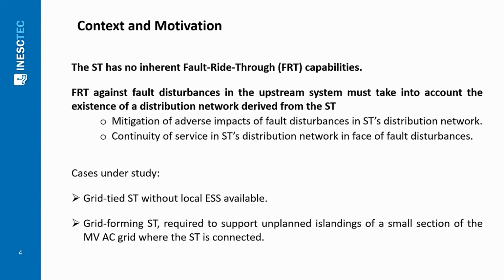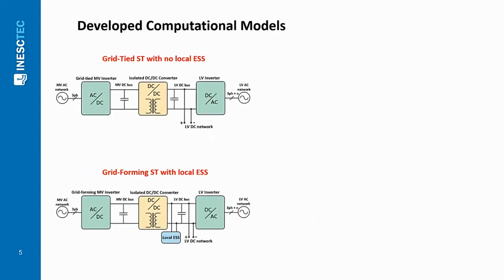The second case study evaluates the provision of fault ride-through in a grid-forming smart transformer which is supposed to support an unplanned islanding of a small section of the medium voltage AC grid where the smart transformer is connected, without power supply interruption, moments after the start of a fault disturbance in the upstream system.